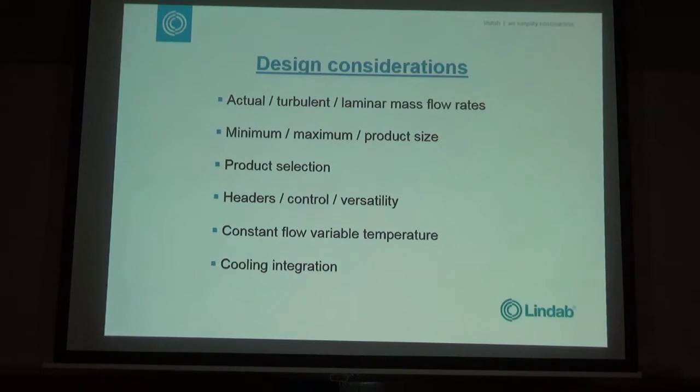Yeah, generally, again, at our previous employer, we used to do a 10 mil pipe and we used to say 0.008. Now, that's probably true, but when you're talking about such small amounts of water, controlling it is as much of an issue as anything else. You know, how you control between 0.008 and 0.01, it's really difficult. So you have to go slightly up on the pump, slightly with the elevated mean temperature as well. Yeah.